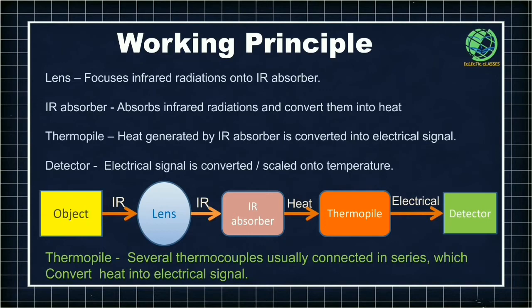First, there is the object — something whose temperature is to be measured. The object is at a certain temperature above absolute zero, so it is emitting infrared radiation. That infrared radiation travels first to the lens. The role of the lens is to focus that infrared radiation onto an infrared absorber. The infrared absorber then converts that focused infrared radiation into heat.